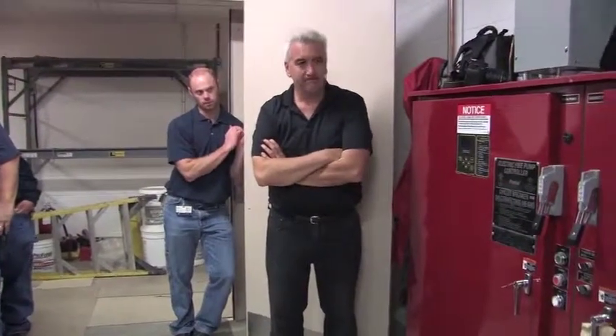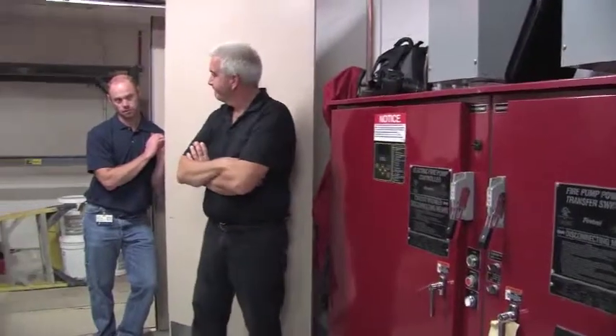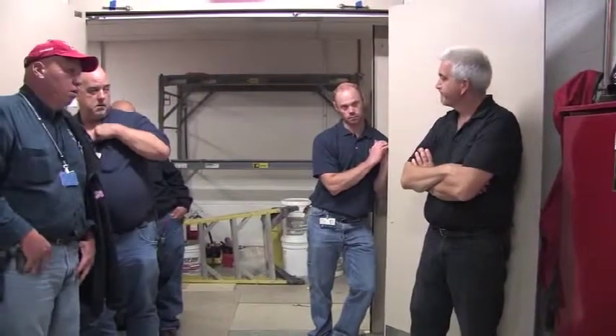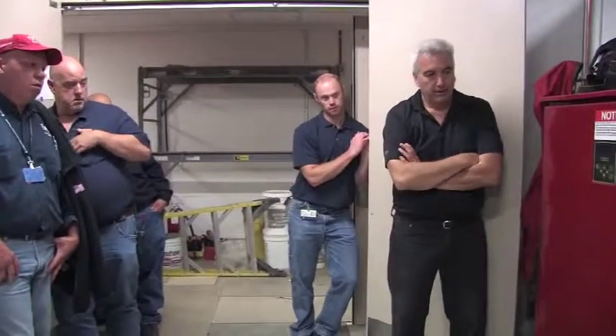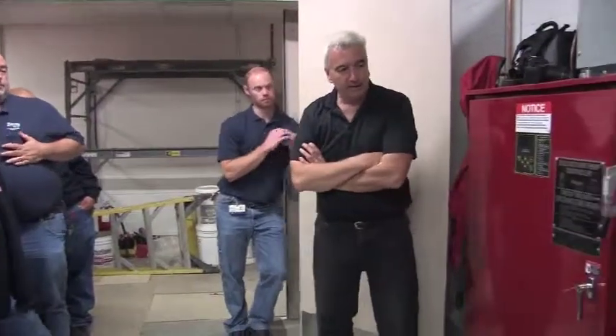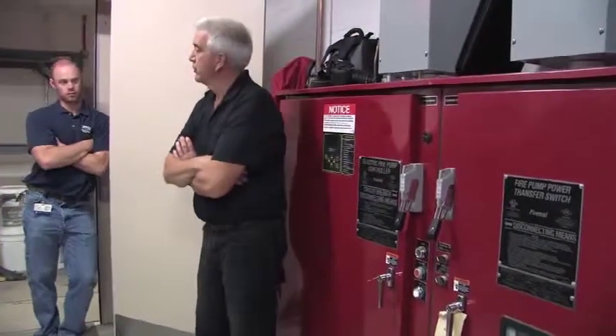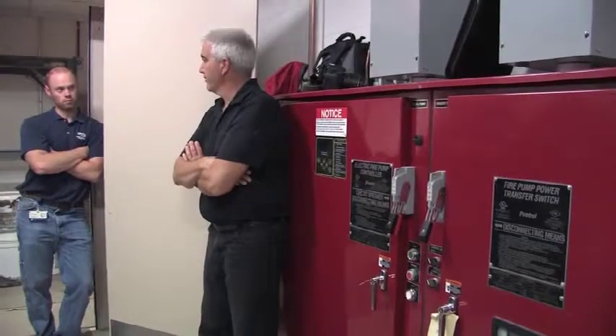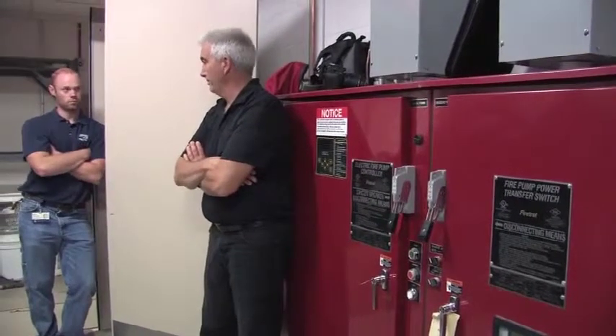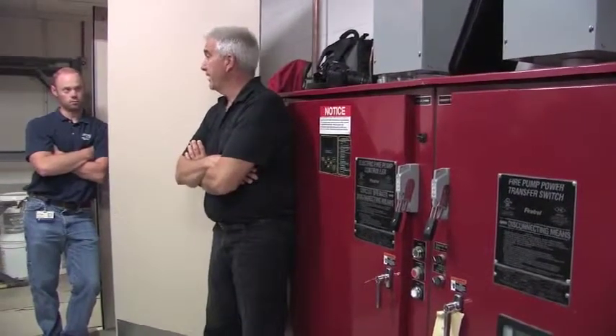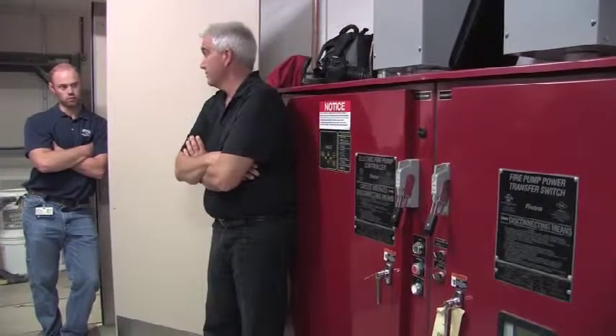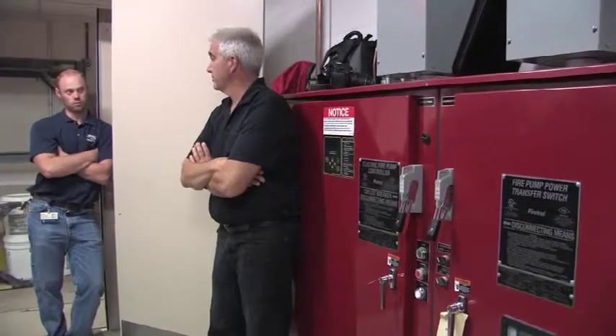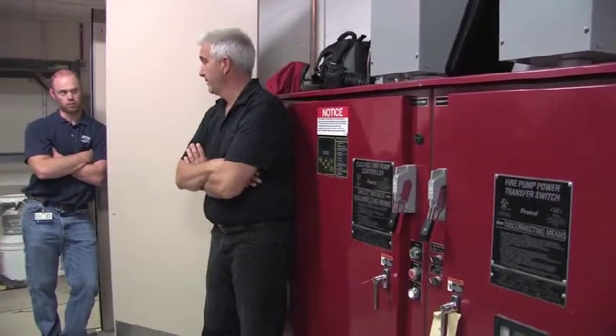What else? Is there a recommended maintenance on these control panels? Well, annual maintenance? Yeah, NFPA 25 says you're supposed to have the controller gone through by a factory authorized person to make sure it's working properly. Correct. So we do offer that for several campuses around here, as a matter of fact. We do it with Beth Israel. We just got done doing it with Israel a few weeks ago.